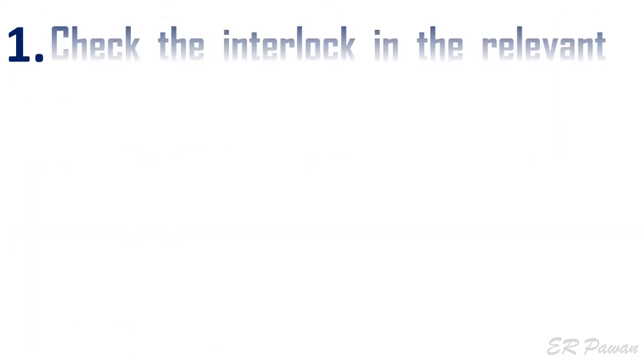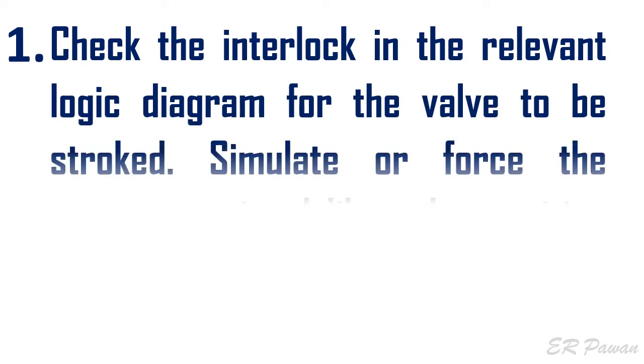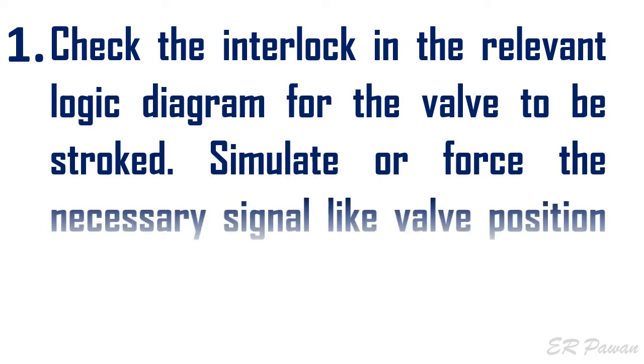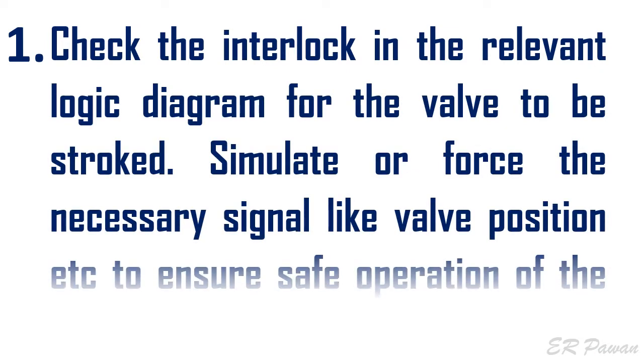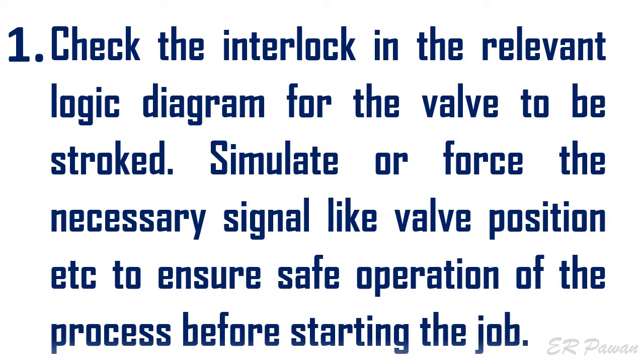Step 1: Check the interlock in the relevant logic diagram for the valve to be stroked. Simulate or force the necessary signals like valve position, etc., to ensure safe operation of the process before starting the job.